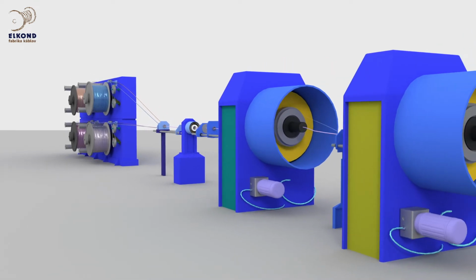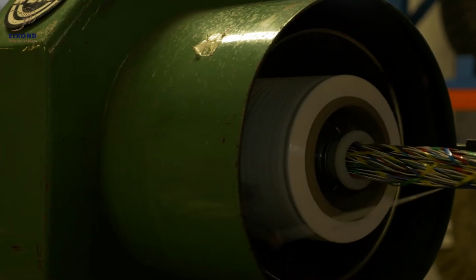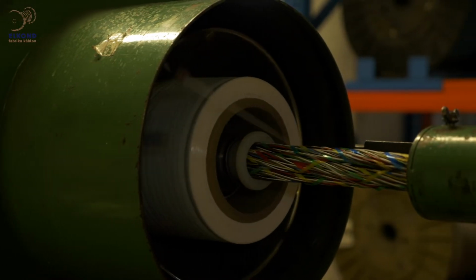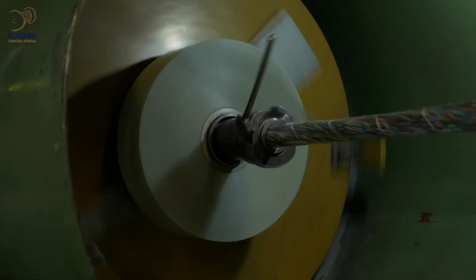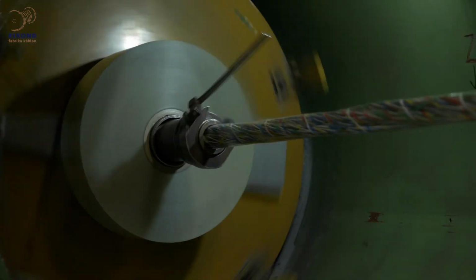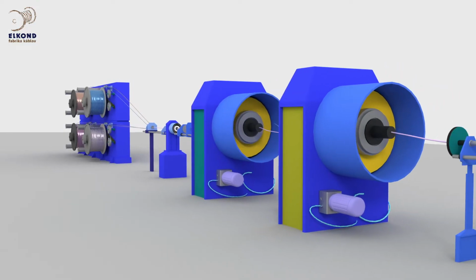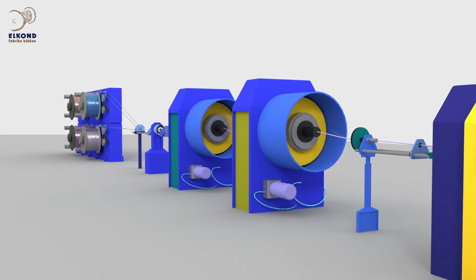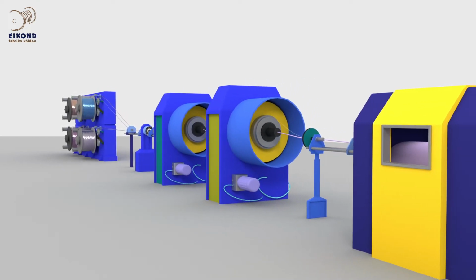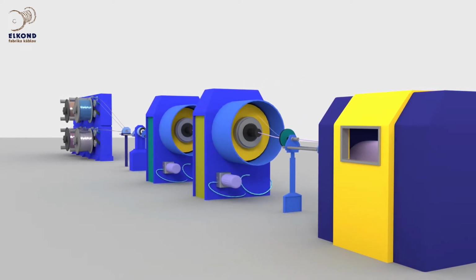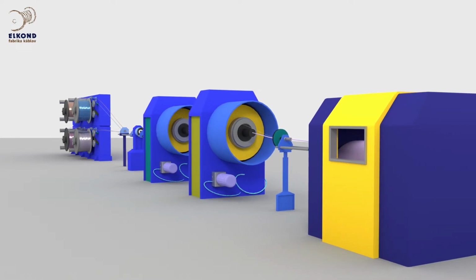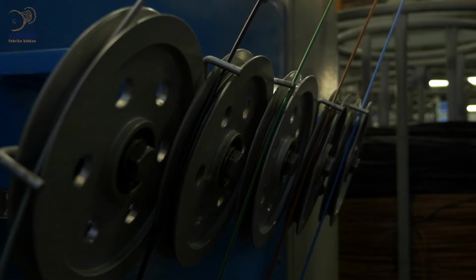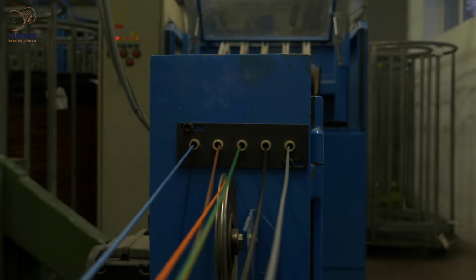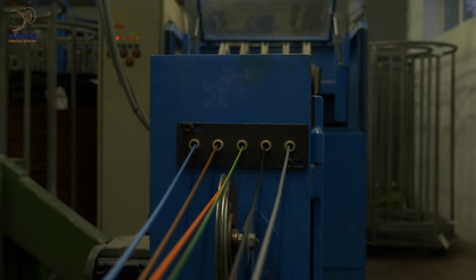The line has also additional machines that apply various protective and screening tapes. Some of our cables consist of up to 400 stranded wires. Production of cable cores can be done in various ways: regular stranding, stranding into subgroups and consequent merge in layers, also called SZ stranding, where the stranding direction is being altered in regular cycles. Stranding method is chosen depending on requested parameters and intended purpose of the cable.